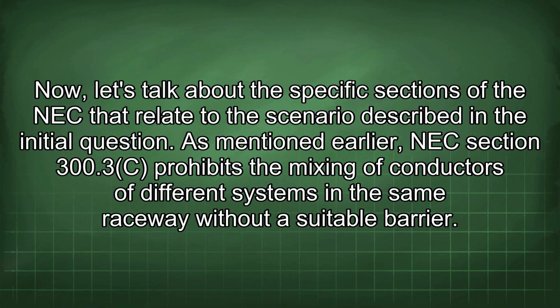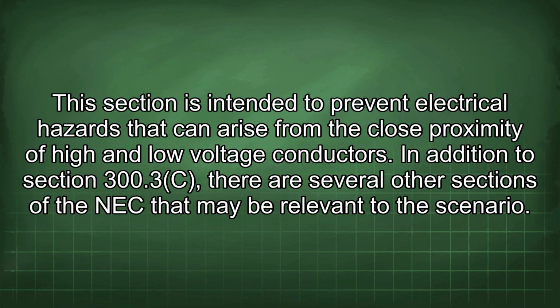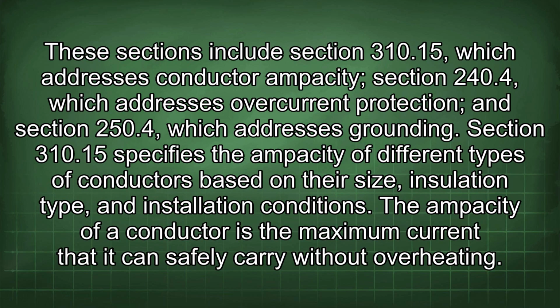Now let's talk about the specific sections of the NEC that relate to the scenario described in the initial question. As mentioned earlier, NEC Section 300.3(C) prohibits the mixing of conductors of different systems in the same raceway without a suitable barrier. This section is intended to prevent electrical hazards that can arise from the close proximity of high and low voltage conductors. In addition to Section 300.3(C), there are several other sections of the NEC that may be relevant to the scenario. These sections include Section 310.15, which addresses conductor ampacity, Section 240.4, which addresses overcurrent protection, and Section 250.4, which addresses grounding.